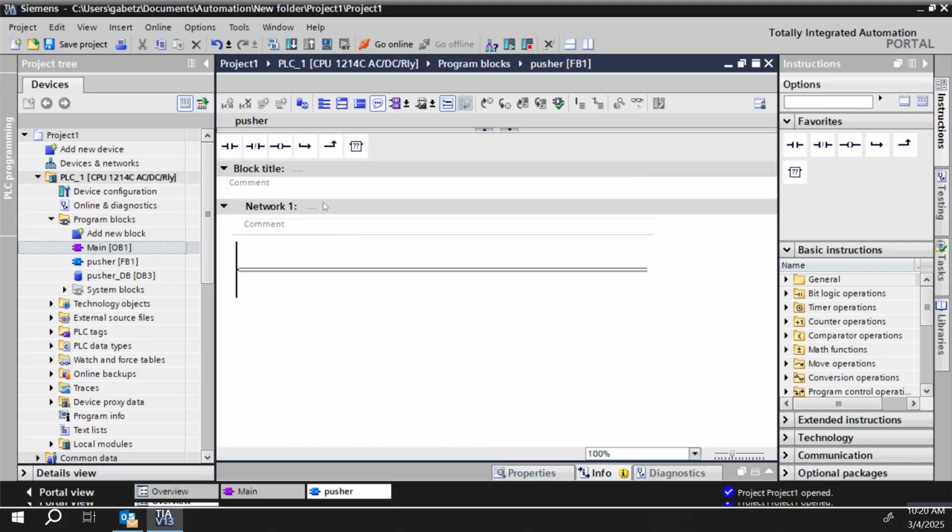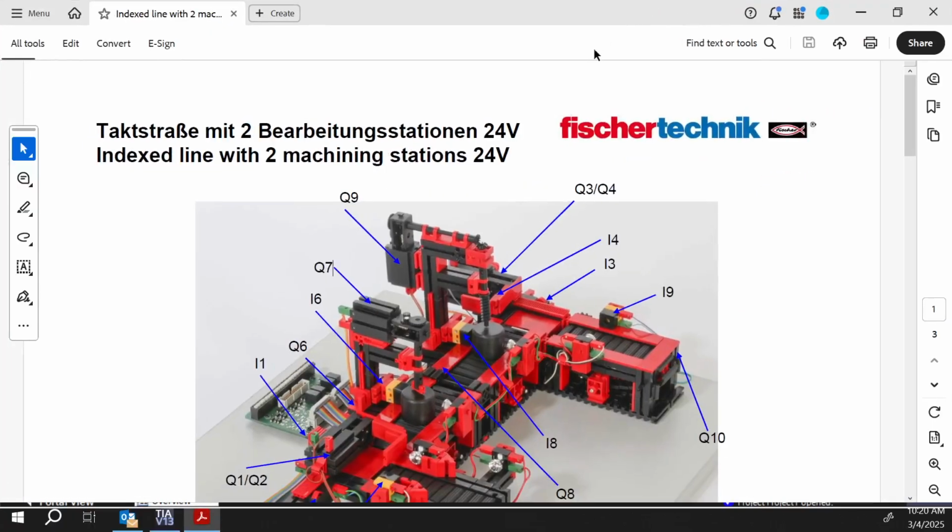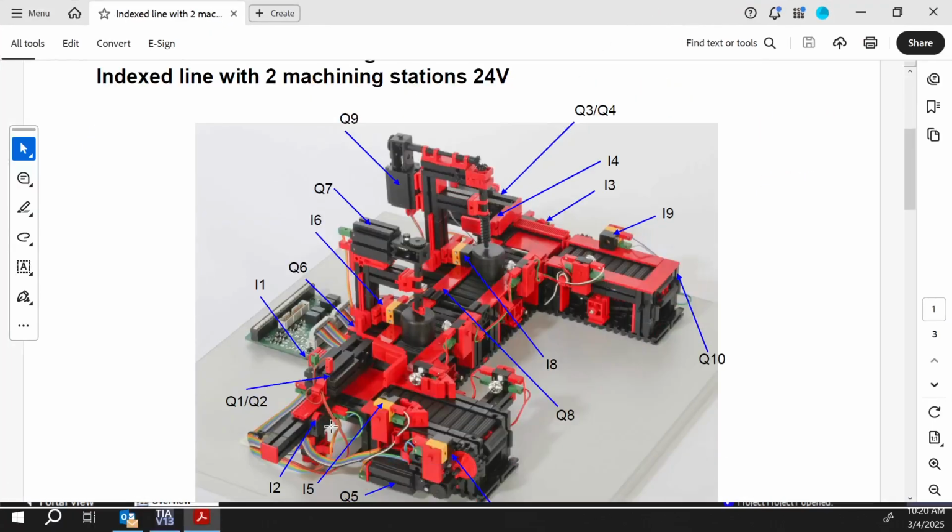Now, you probably are going to need more inputs. You're going to need a signal, like, when should I go forward? And sadly, this is one of those things that the conveyor trainer here is missing. There's no sensor that tells you there is a part in this location. You are actually relying on the previous conveyor to tell you, hey, I've put a part onto you. This one actually bothers me. One of those locations should have a sensor.